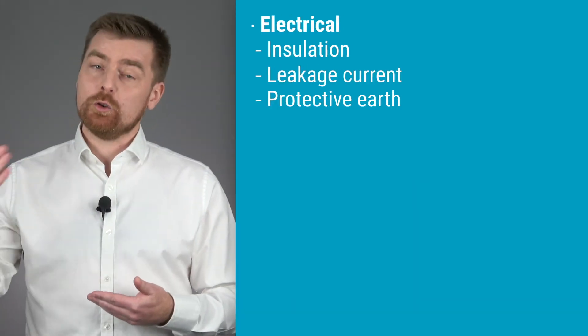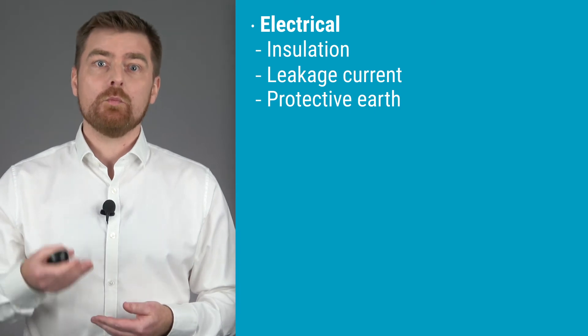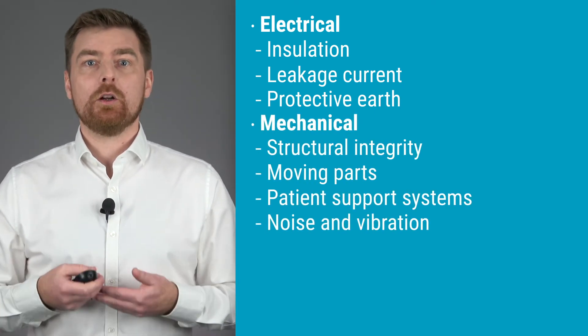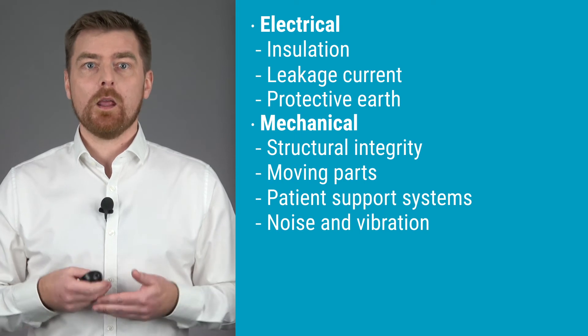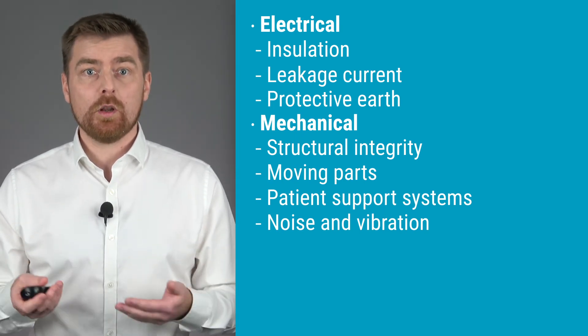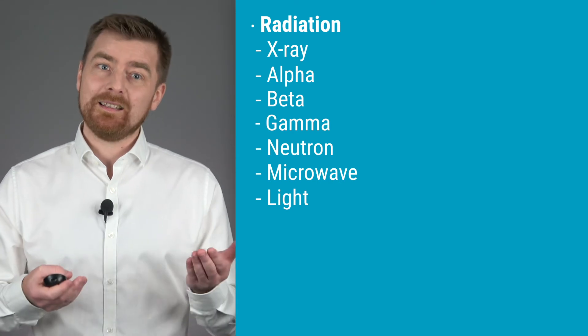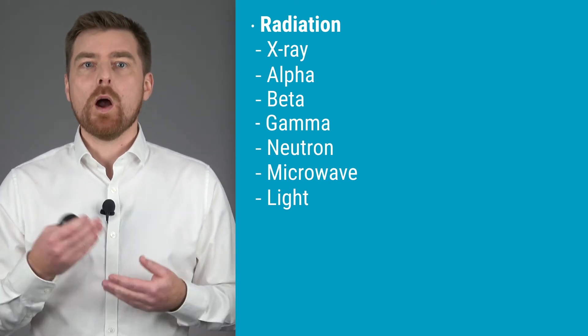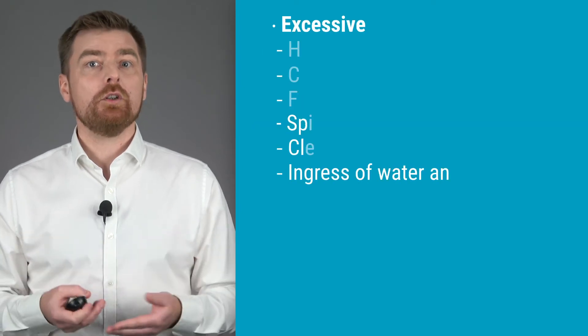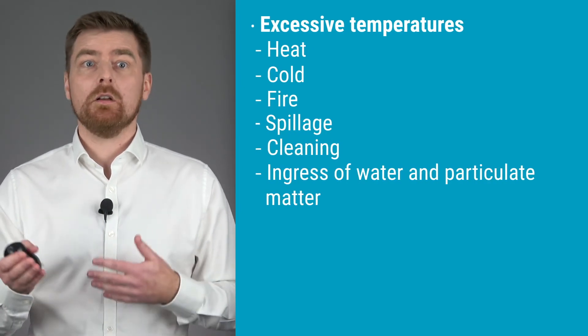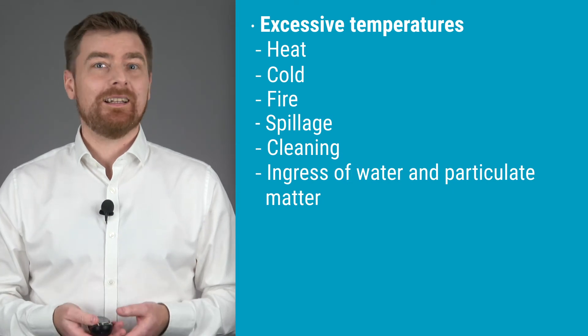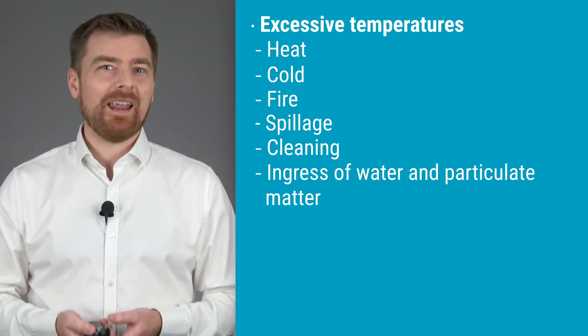Some requirements are more detailed than others. The requirements include electrical requirements such as insulation, leakage current, and protective earth. Mechanical requirements include structural integrity, moving parts, patient support systems, noise and vibration. Radiation requirements include x-ray, alpha, beta, gamma, neutron, microwave and light radiation. Temperature and other hazards include heat, cold, fire, spillage, cleaning, and ingress of water and particulate matter.